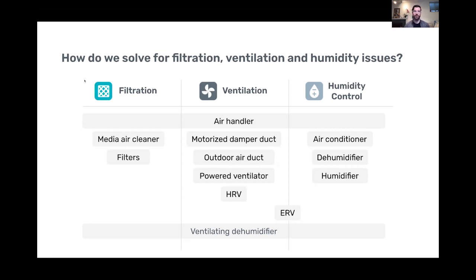You've got powered ventilators. This is just the ability to push in outdoor air without a heat exchanger at a higher CFM. And then you've got HRVs bringing in a balanced ventilation into the home, but without an enthalpy membrane. So the ERV is something that's going to retain more moisture or maintain the relative humidity inside of the home better than an HRV due to that membrane. And so that almost borders on being something that helps control humidity, which is why we put it across the two sections.